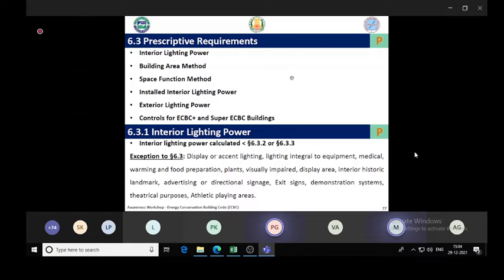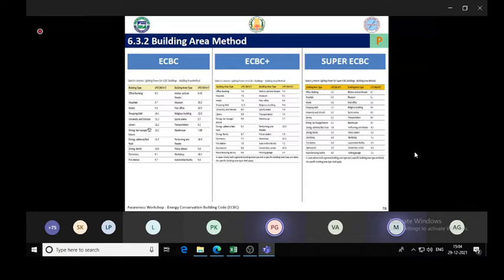So basically it deals mainly with the lighting power density, LPD. This is almost like what we normally use in IGBC and other certifications, so it's something almost similar to that. The LPD requirements are given for ECBC for different spaces, in watt per square meter. Again, we have two methods, the building area method or the space by space method. The installed LPD should be less than the LPD specified in this table for the type of the building. And generally it is quite easy to meet this. If you are using LED and you have a reasonably good lighting lux level design, then it's easy to achieve this LPD. Normally we get a good number of savings from the lighting section.